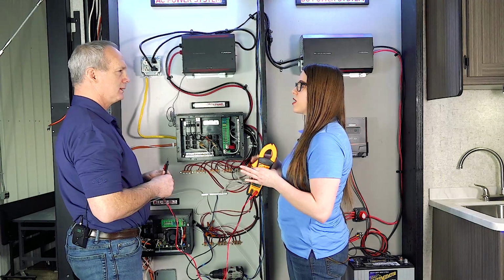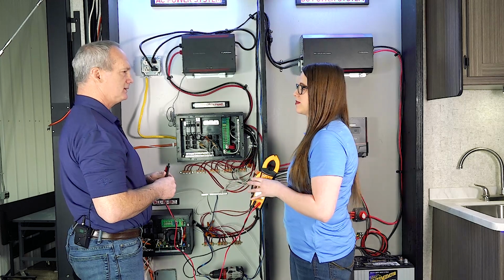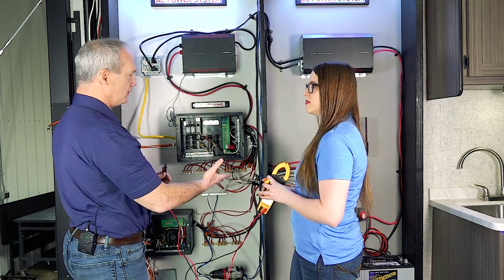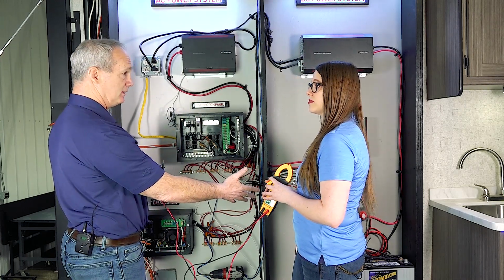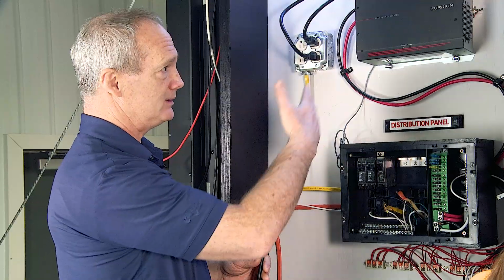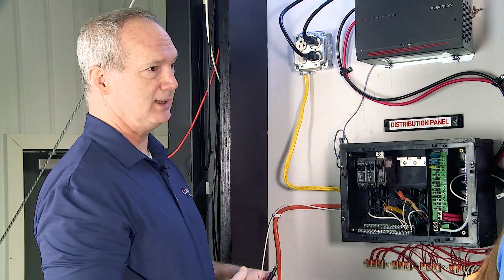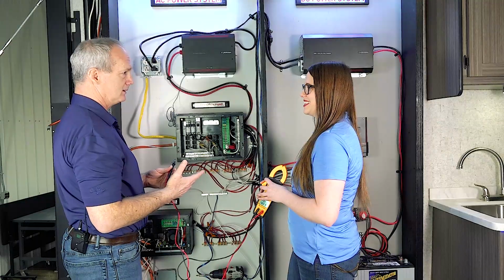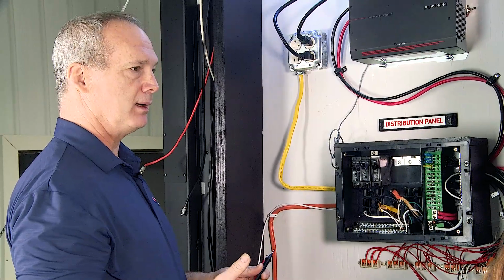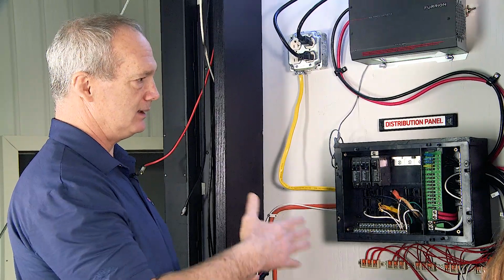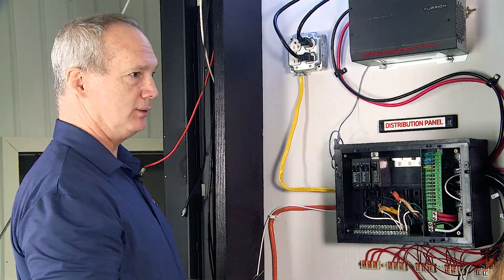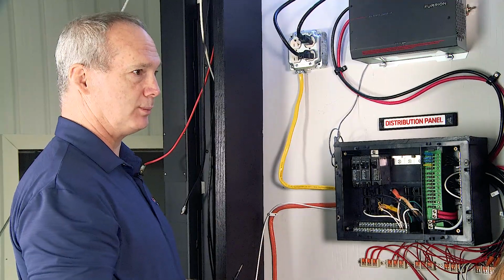What happens if we're outside of those measurements? If it's too high, it's supplying too much voltage and can cause damage to the battery. And if it's low voltage, you can just guess—your guess is as good as mine, weird things can happen. Low voltage is a common problem in RVs, and it starts with the battery, but this will help troubleshoot that and make sure we know what the actual problem is.